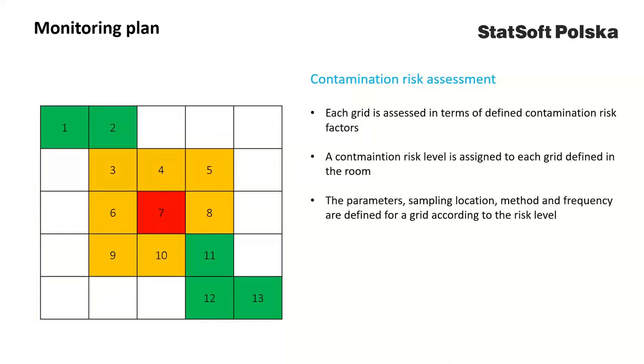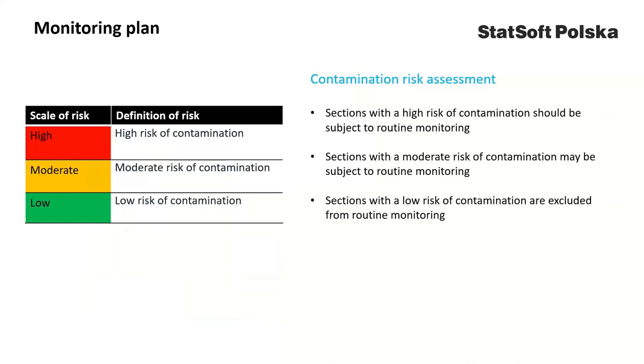Having defined risk factors and how to analyze them, we can evaluate each grid using contamination risk factors and assign a risk level to each grid. The parameters to be monitored, sampling locations, sampling methods, and frequency are defined for a grid according to the risk level. Sections with a high risk of contamination should be subject to routine monitoring. Sections with moderate risk of contamination may be subject to routine monitoring depending on the results of the qualification study. Sections with a low risk of contamination are usually excluded from routine monitoring, although some grids may be added as reference points.